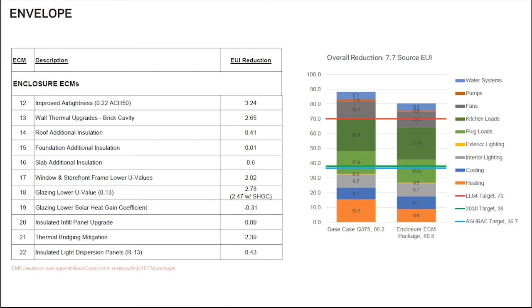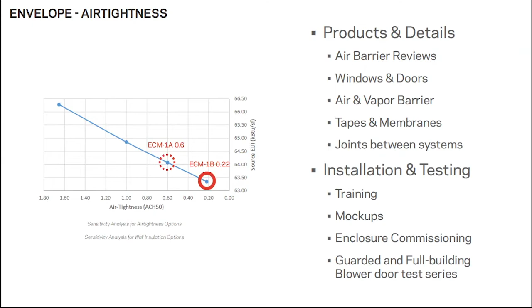This one is air tightness. The dot on the upper left represents the base case level of air tightness, and the other dots are other targets we looked at. Ultimately we went with the most stringent approach, equivalent to the passive house air tightness per facade area requirement. The dashed circle is around 0.6 air changes per hour, but using the facade area approach, it was more like 0.22 air changes per hour.